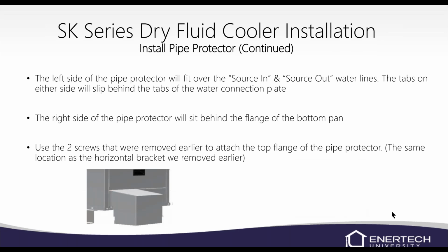The left side of the pipe protector will fit over the source in and source out. The tabs on either side will slip behind the tabs of the water connection plate. The right side of the pipe protector will sit behind the flange on the bottom plate, and the 2 screws that we removed earlier will attach the top flange of the pipe protector. For some reason you lose those screws in the grass or whatever, they're just a self-tapping 5/16 screw. I'm sure you'd have one on your truck if you lose it. So not a big deal.